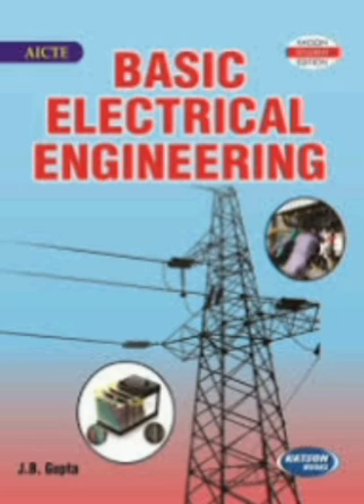Y-delta. This connection is used for step down applications. Delta-Y. This connection is used for step up application, except in distribution systems where delta-Y is used for step down application for mixed loading. Y-Y. This connection is quite attractive for HV applications. It is not generally used without a tertiary delta.